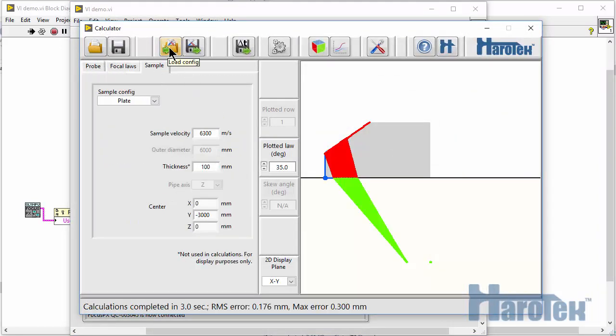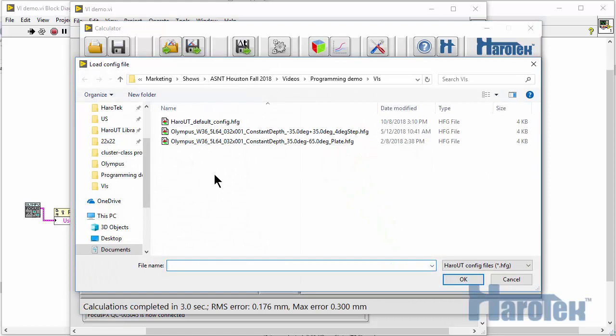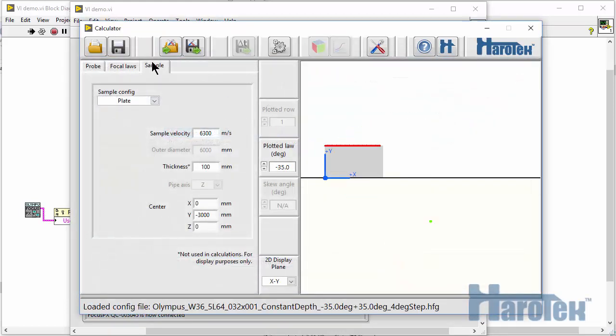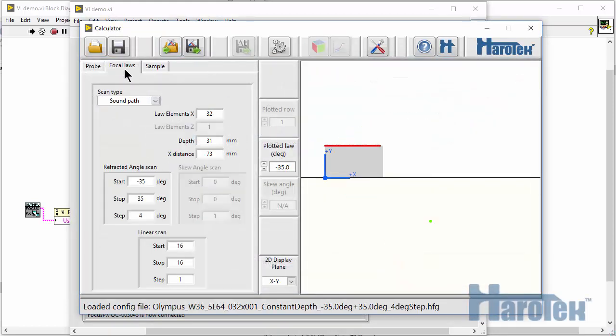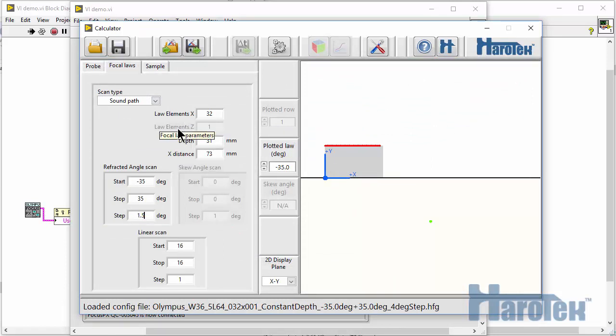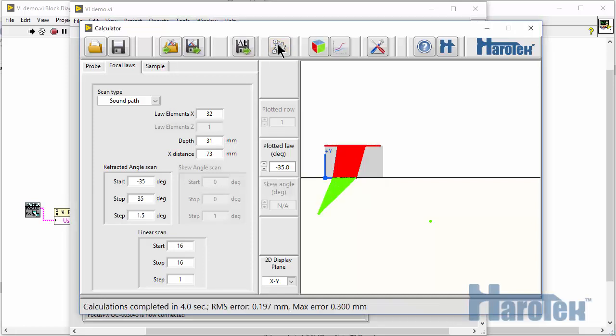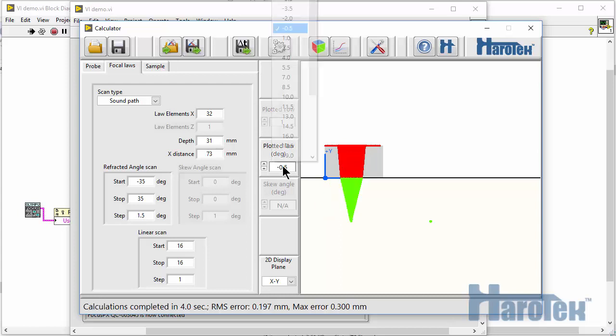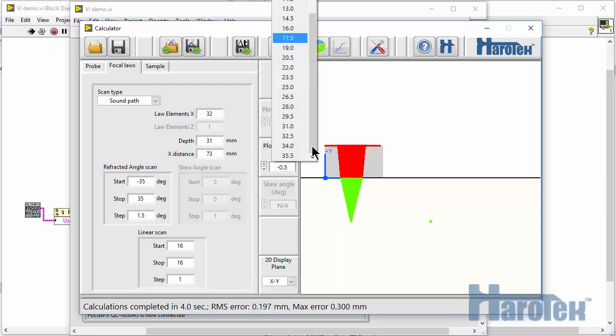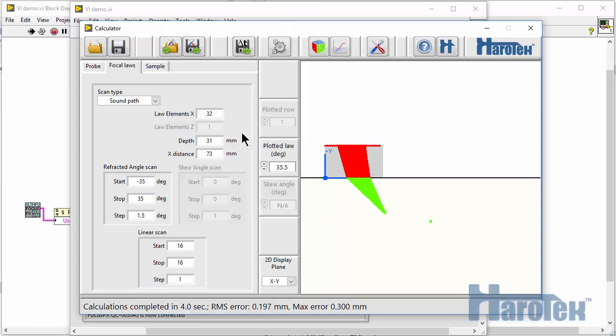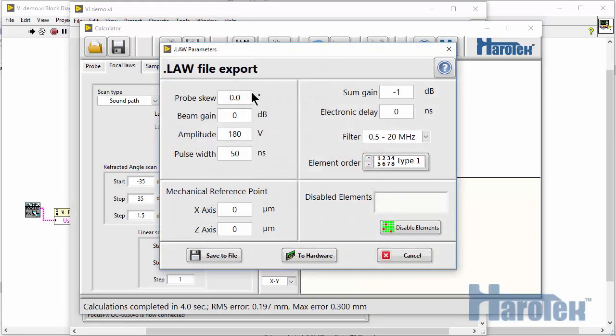The parameters of a probe with a flat wedge are loaded. The Angular step is changed to 1.5 degrees. Then I run the calculations. After the calculations are completed, the delays can be uploaded to the Focus PX.